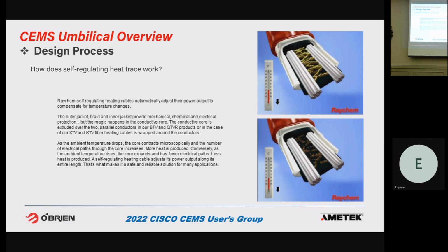If that's acceptable to a customer, they don't have to use temperature control. If they want a tighter temperature band, they can use a temperature control. If you're using a tracer whose maximum temperature is 250F, and you want to maintain 200F, so you're hitting 200F on the cold day, on the hot day of the year maybe you're hitting 285 or something. If above that is not acceptable, then you have to use temperature control. So just because it's self-regulating doesn't mean you don't need temperature control.